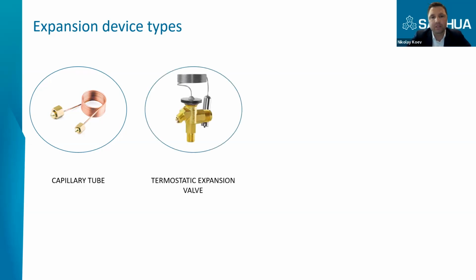The most efficient and successful mechanical expansion device is actually the thermostatic expansion valve. It regulates the superheat on the evaporator and adjusts the refrigerant flow to the evaporator. Here we also have some limitations in order to achieve maximum energy efficiency, and it comes, on one side, from the superheat, because the thermostatic expansion valves cannot operate at a very low superheat. Usually they have static superheat 5 or 4 kelvins. The set point is in most cases 7 or 8, and usually they operate at 10 Kelvin or 9 Kelvin, which means that, as you may know, the lower the superheat, the more efficient the system.